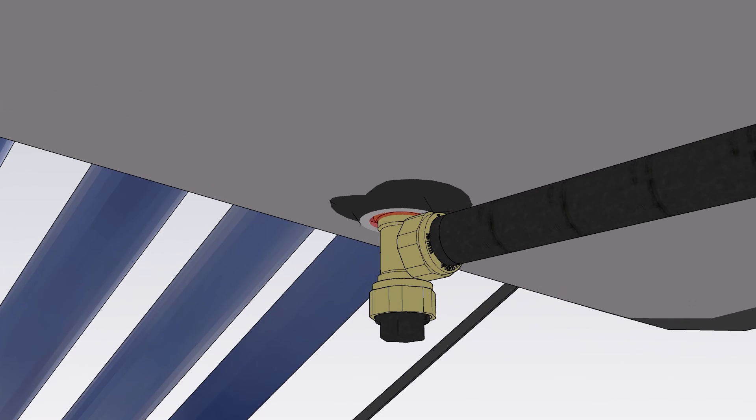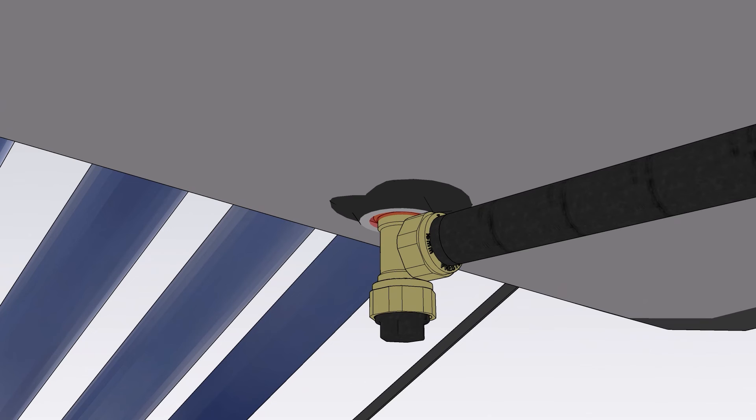Cold water inlet. A three-quarter inch male draincock will be installed on the cold water inlet side and must have PTFE tape or hemp wrapped around the thread before installing. When draining the geyser, ensure a hose is attached to the draincock which leads to the gutter as to avoid injuries from the hot water being expelled.